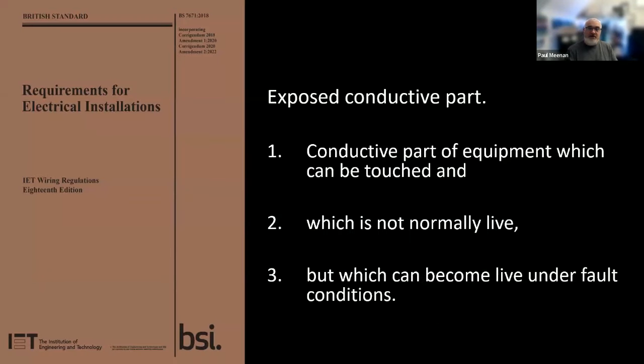Now, I adopt simple rules to learn this stuff, and I like the rule of three. So what is an exposed conductive part? Well, in the wiring regulations there is a paragraph. But if you're an apprentice or a learner, get a highlighter pen. Highlight things, break the sentences and paragraphs up so that you can break it down into simple stuff. So an exposed conductive part is a conductive part of equipment which can be touched. Okay, but it's not normally live. Fine, but it can become live under fault conditions. Three parts to that, a very simple rule to remember. It's a part of equipment which can be touched, it's not normally live, and it can become live under fault conditions.